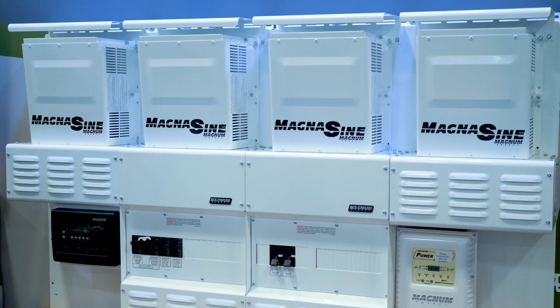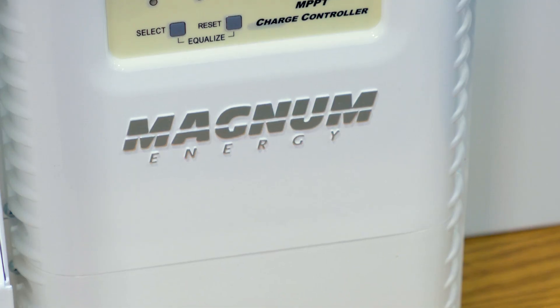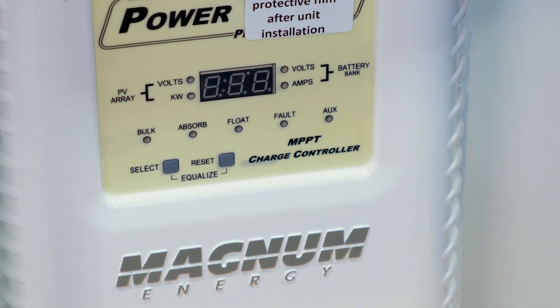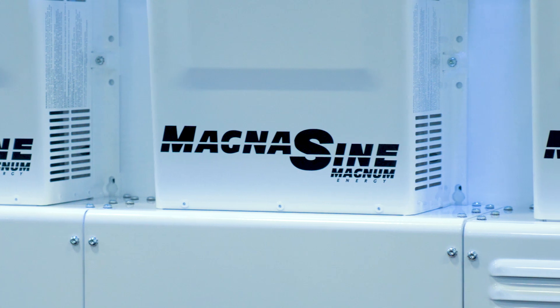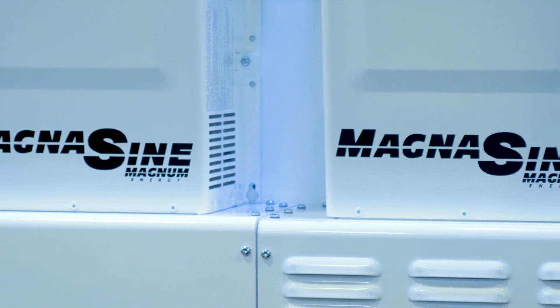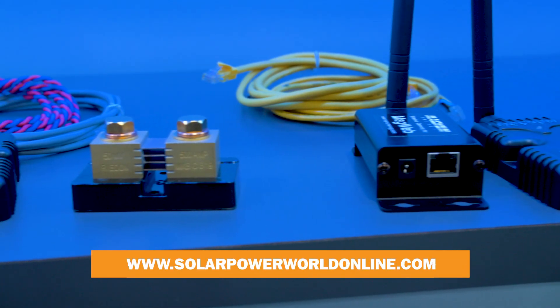Using our CC-CV profile, you can charge most any lithium-type batteries. That CC-CV profile is fully configurable as far as voltage set points, maximum charge current, end amp time, and end amp current. We also have the standard profiles found on all Magnum products, which are lead acid, flooded, AGM, and gel.